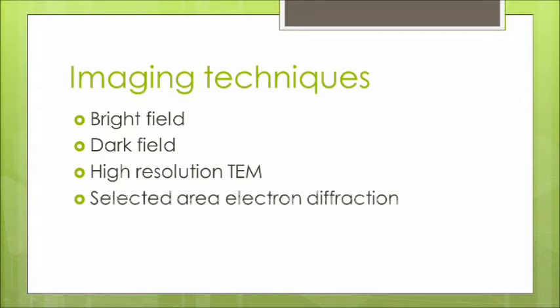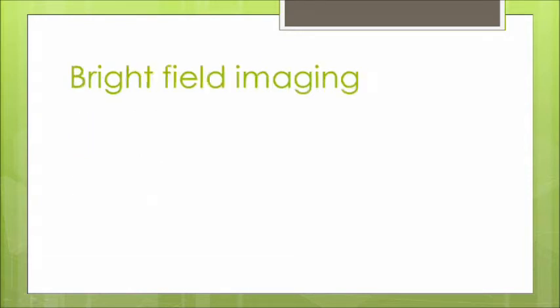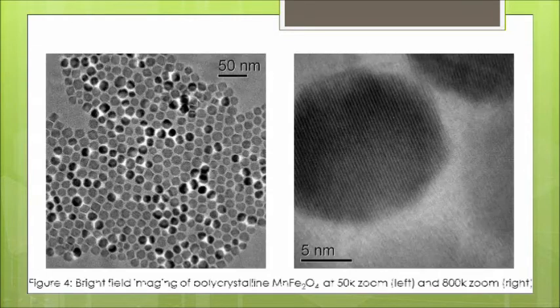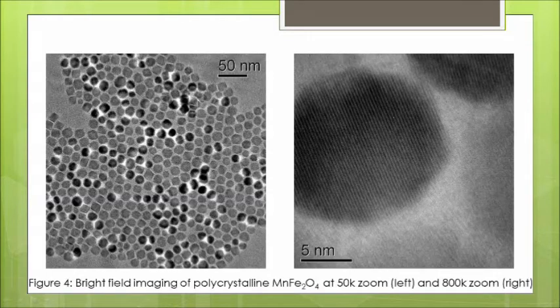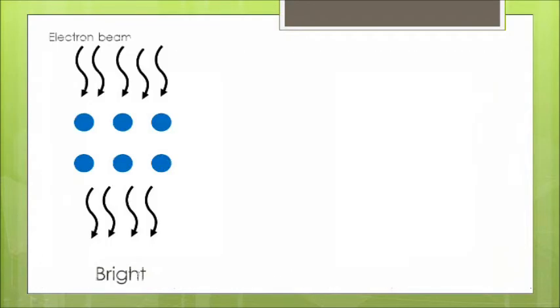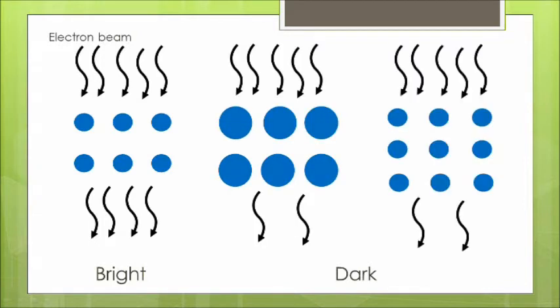There are different imaging techniques that one can employ with the TEM. The most common and simplest is the bright field imaging technique. This technique simply uses the transmission and absorption or scattering of electrons from the sample. The bright areas are where the electrons are able to pass through the sample, while the dark areas could represent areas with atoms of higher atomic mass, or simply a thicker area.